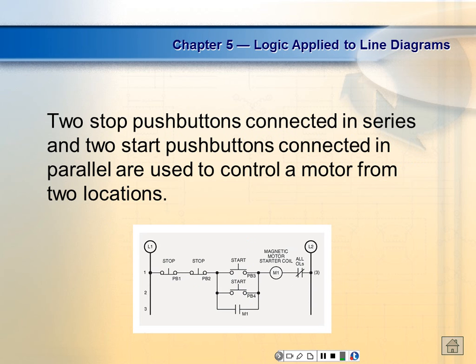Of course, now all of a sudden we don't have a NOT. This is no longer a NOT. This is what? No. Any one of these buttons would turn it off, right? You understand? This is an OR. Any button will start it. So we can have multiple start-stop stations.